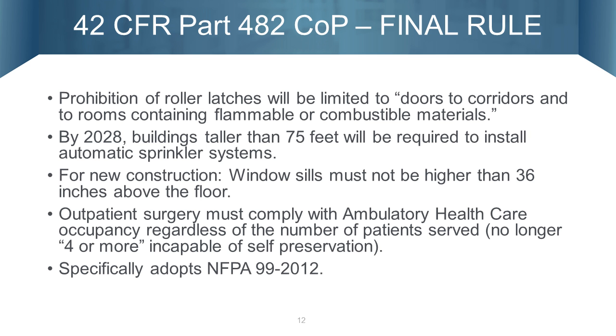Okay, let's look into some of the changes that were made when CMS adopted this as part of their conditions of participation. They again prohibited roller latches, which is what the stance they had taken before under the 2000 edition of the code. Basically, no change there. We cannot have roller latches on doors to corridors or rooms containing flammable or combustible materials.